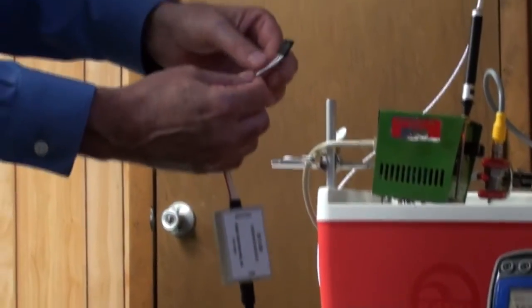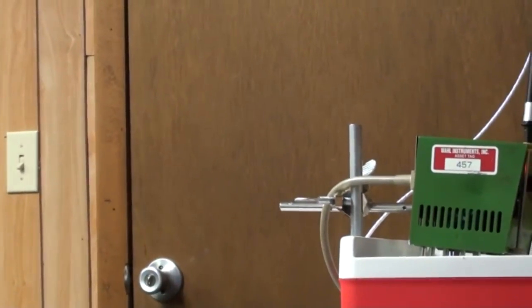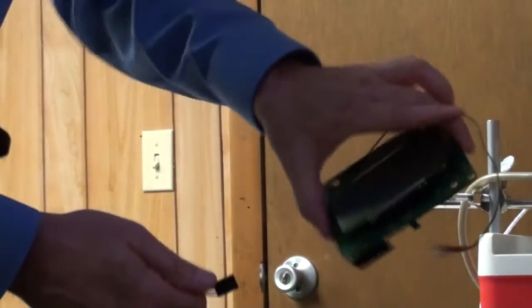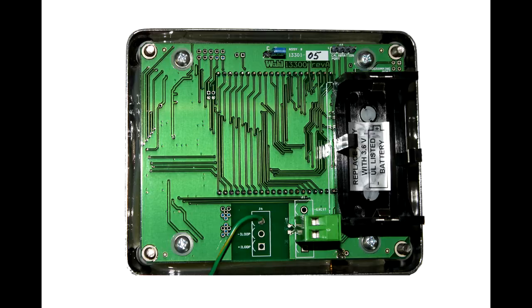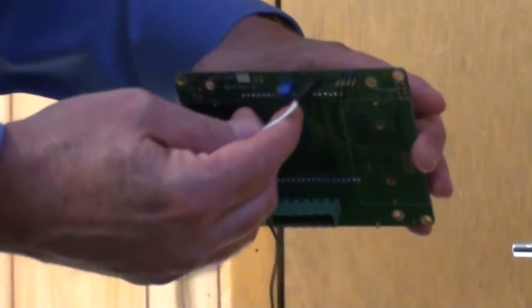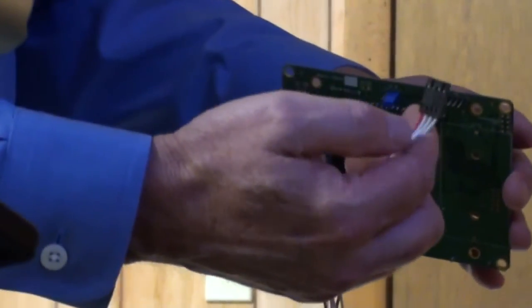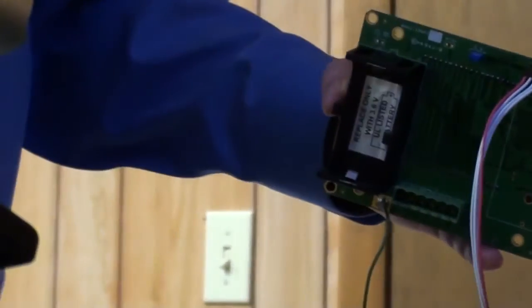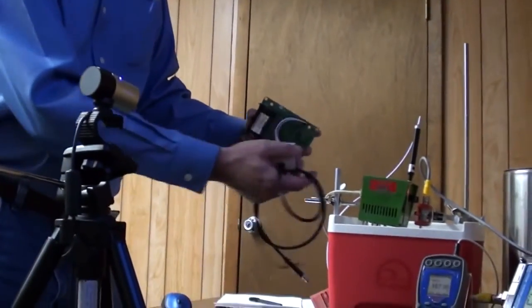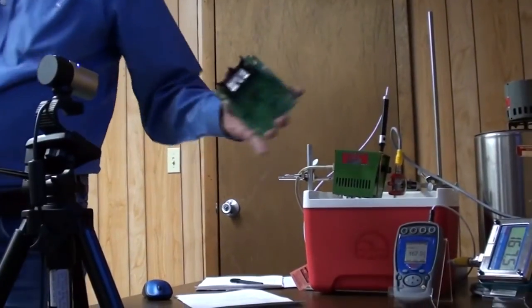The red wire indicates pin 1. And then on the PC board, and this is just the PC board only, yours certainly will be mounted in the cover assembly, we have 4 pins up here. This blue jumper is where you change it between degree F and degree C. And there are 4 pins to the right of that, labeled calibration port, J3. The pin that's closest to the F/C pin is pin 1, indicated by a small number 1 there and a number 4 on this end. So you want to make sure that red wire gets plugged in to that pin, and that's the proper connection. Once you do that, this unit will connect via this interface, and that's how we load data into here and do the calibration.